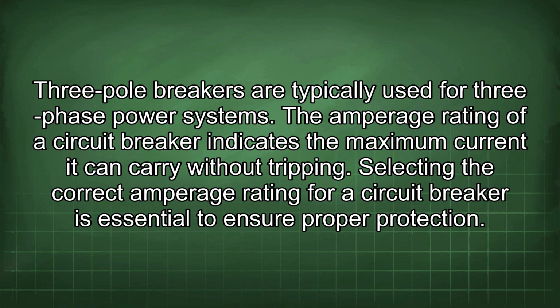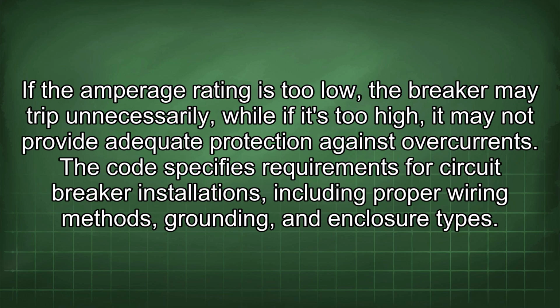The amperage rating of a circuit breaker indicates the maximum current it can carry without tripping. Selecting the correct amperage rating for a circuit breaker is essential to ensure proper protection. If the amperage rating is too low, the breaker may trip unnecessarily, while if it's too high, it may not provide adequate protection against overcurrents.